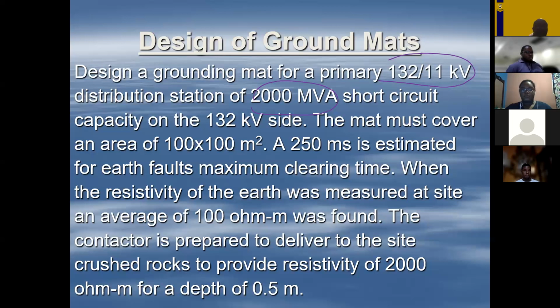You have 100 ohm meter at the site, relatively low, but that's what we have. And the contractor has access to some crushed rocks, which should give you an additional 2,000 ohm meter for a depth of 0.5. Right? So this is some of the information that you would have had, and you know what you have to work with, okay?